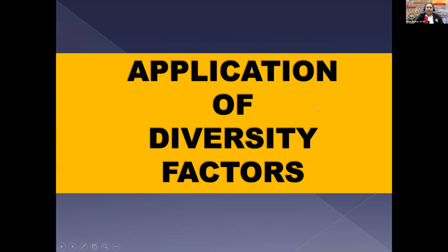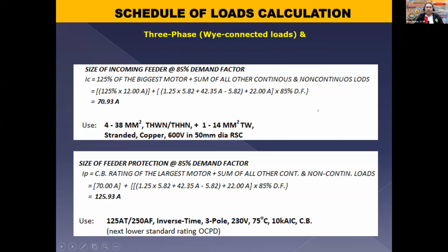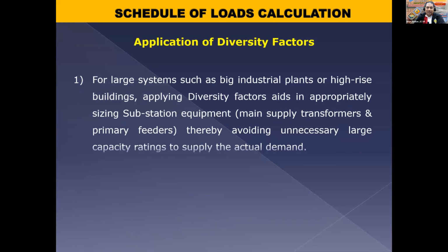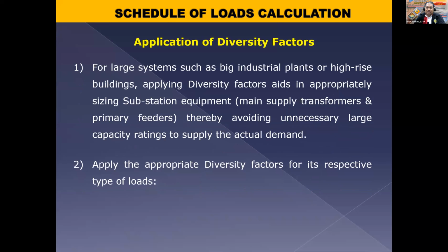Sige. So next, tapos na tayo sa load schedule. Na-size up natin si branch circuit tsaka si feeder circuits natin, no? So the last step that we need to do is the sizing of our main switchgears or the transformers, no? So at this portion, dito na papasok si diversity factor, no? So for large systems such as industrial plants, appropriate ito si application ng diversity factor para hindi ma-oversize si transformers natin or yung mga feeders natin.